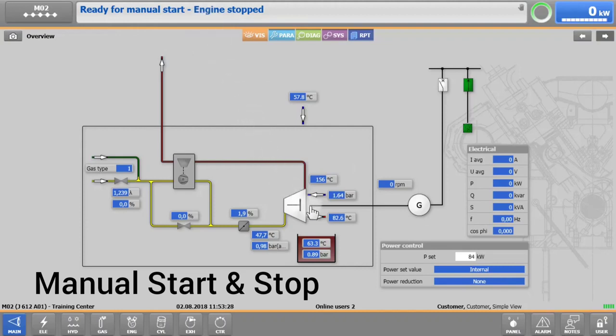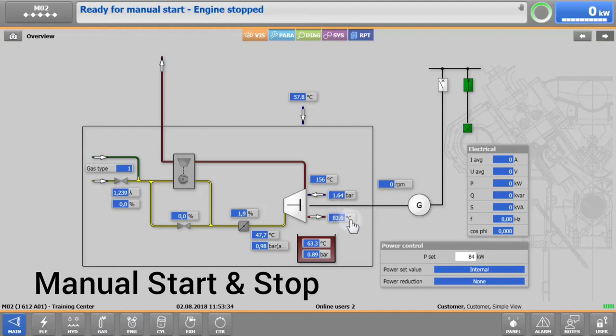Be sure that the jacket water temperature has reached 55 degrees Celsius or 131 degrees Fahrenheit before starting the engine. Synchronization at a lower temperature must be avoided in all cases.